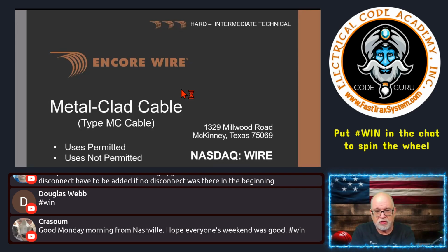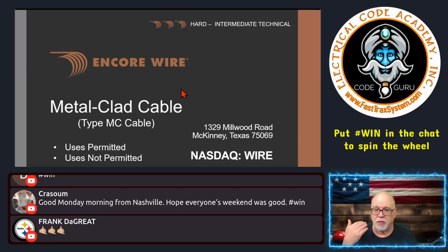If you're changing a service, then you have to put an emergency disconnect on it if it's a residential application. So you've got to work closely with your jurisdiction. But at the end of the day, if there is a disconnect somewhere, so if you're upgrading the panel, then maybe the disconnect's outside. The way you say it, it's a meter and disconnect, and you're doing the inside. If you're doing a simple change out, 200 for 200, 150 for 150, then check with your jurisdiction.